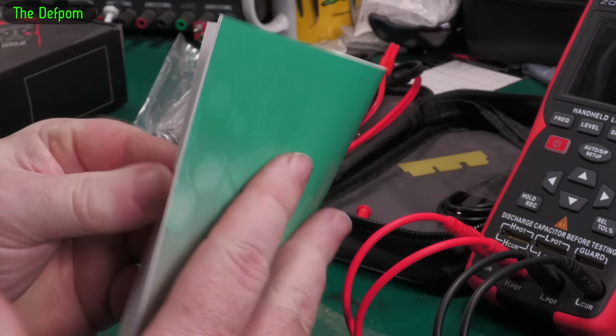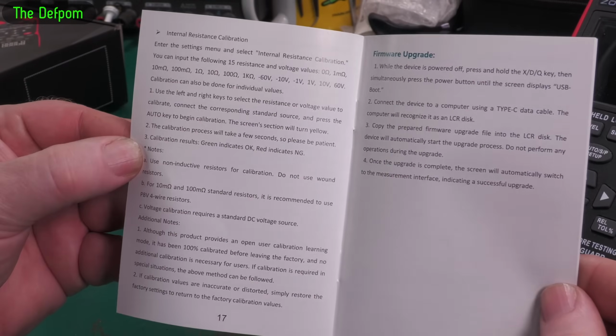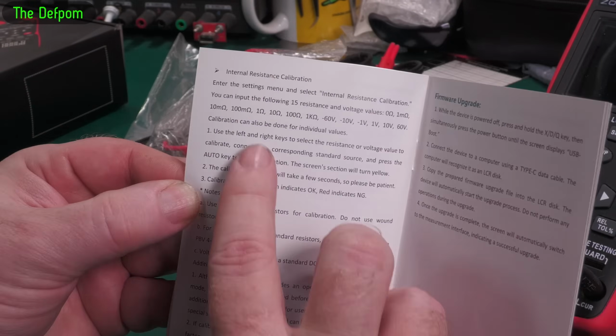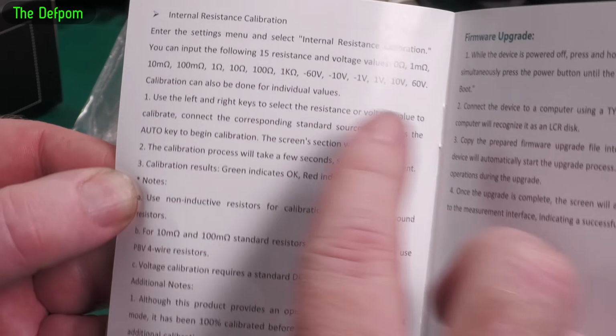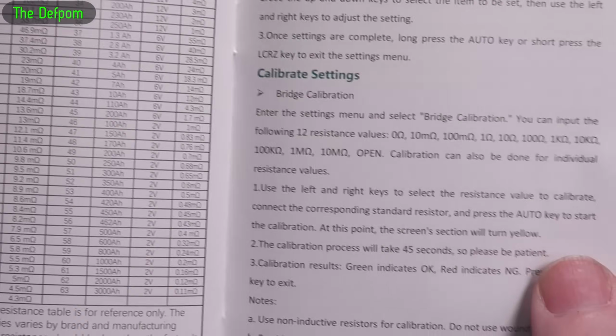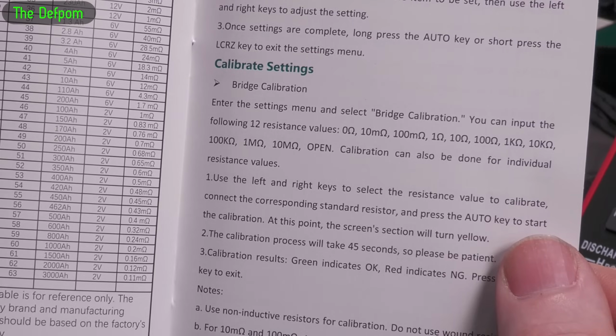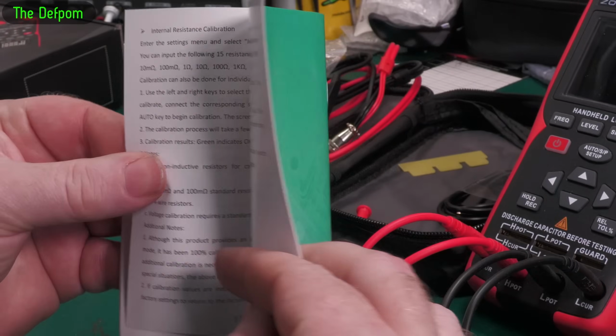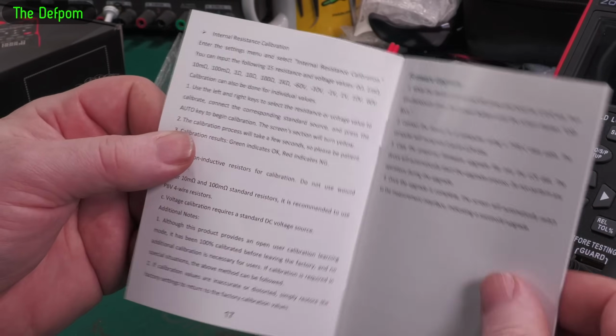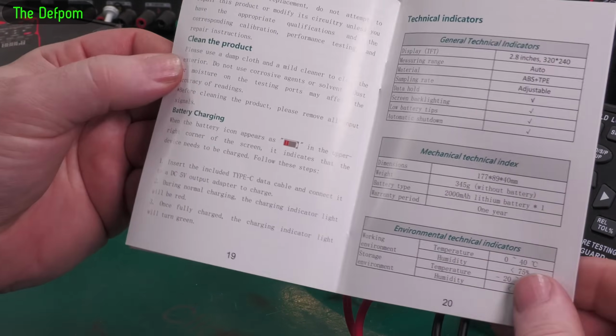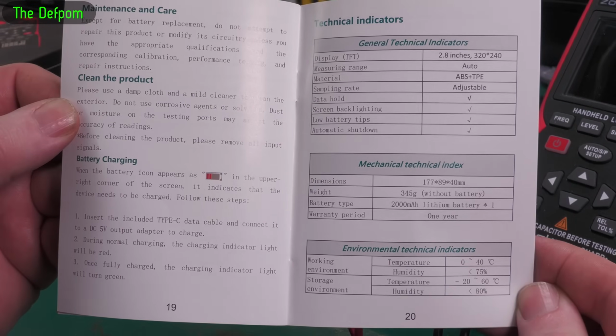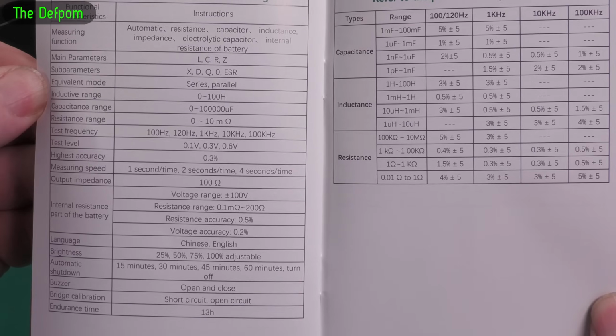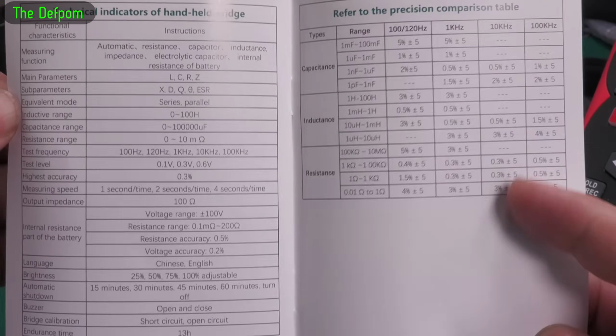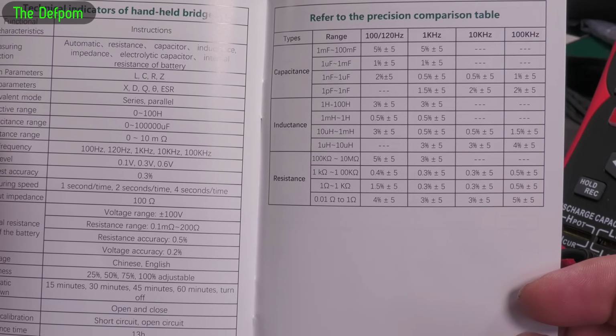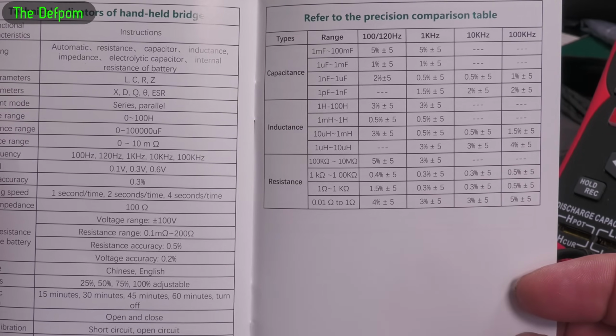You can calibrate this thing as well if you need to do that. Obviously it comes calibrated already, but you need to have all of these resistances and standards for doing calibrations. Also you need a decent voltage source if you want to do voltage calibration, which is part of this one as well. So if you do want to do calibration, make sure you've got all the gear to do it first. And more specs on the back there. These are the specs which you may be caring about, or the tolerances in more detail there about what the actual accuracies are for each particular function and range.